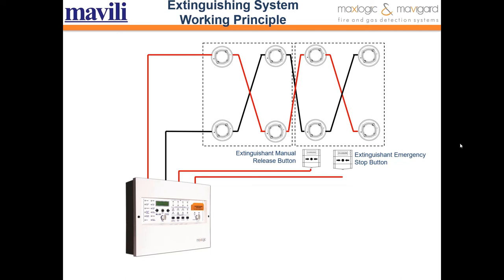Let's talk about the extinguishing system working principle. First, the priorities of fire effects — such as smoke, temperature, or flame — are determined in the location where the gas extinguishing system will be designed. Cross-zone detection is done with at least two detectors in each zone, and the detector type of each zone must be different, such as smoke and temperature. If there is a suspended ceiling, raised floor, cabinet, or cabinets in the area, separate detection should be made in each section.